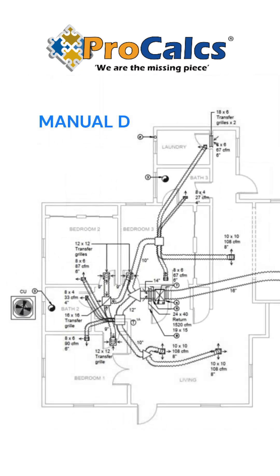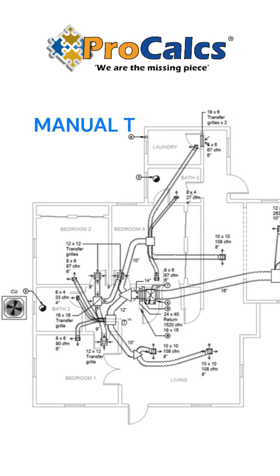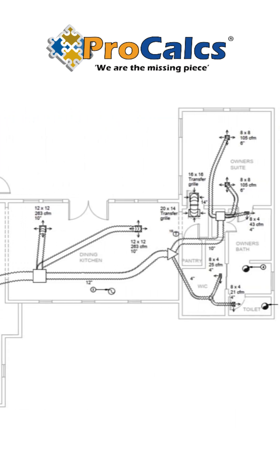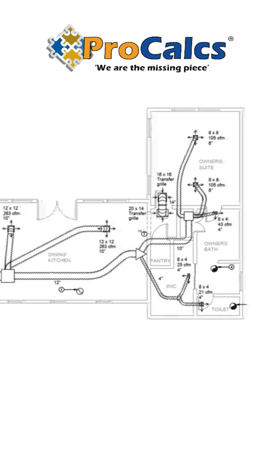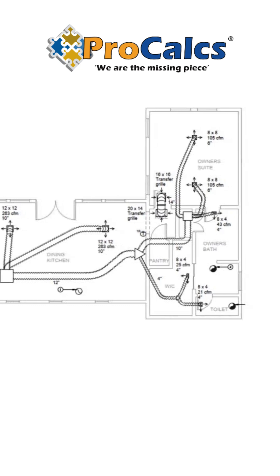We size the ductwork based on Manual D, and we place the supplies and returns based on Manual T. We determine the most efficient and practical routes for ductwork to ensure that the ducts can deliver the appropriate amount of conditioned air to meet the load demands of each zone.